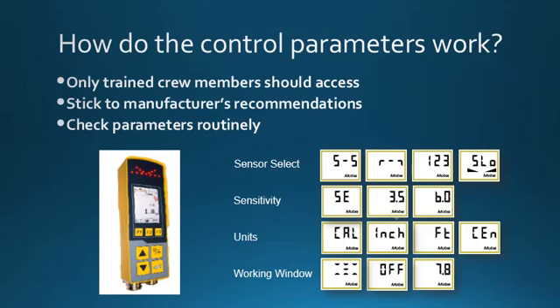Independent of the brand of the grade and slope controls, there will be a number of options or settings that can tune the performance of the system. We already talked about the valve calibration, but there are a number of other parameters as well, such as sensitivity, working window, sensor selection, etc. Only trained crew members should be accessing these. Any change that is made can just as easily make the system perform worse. Only someone who knows what they're doing should be looking at these.